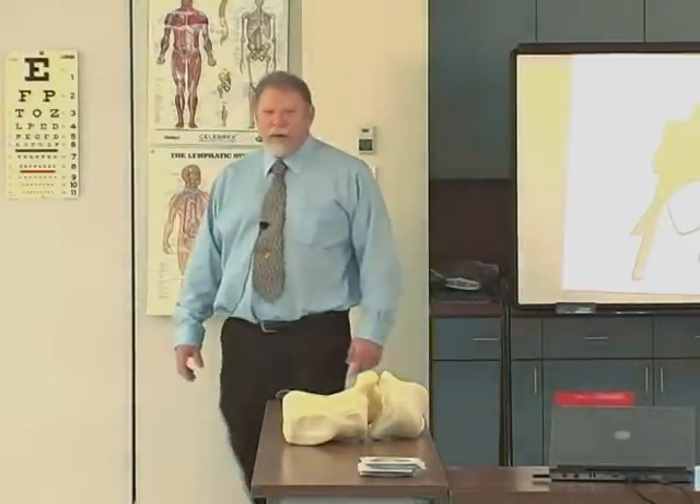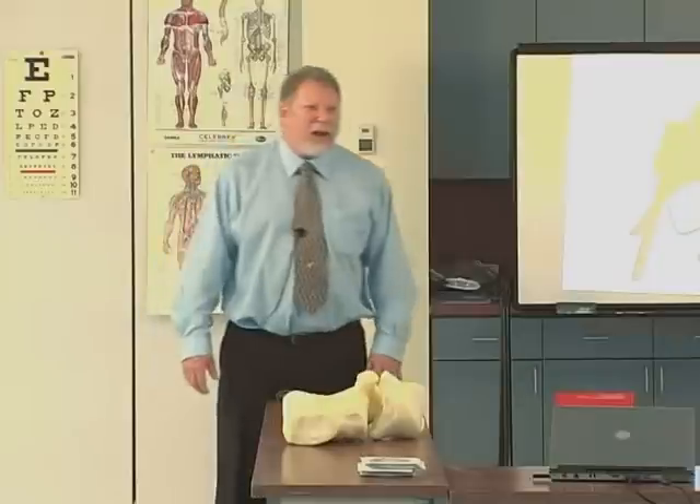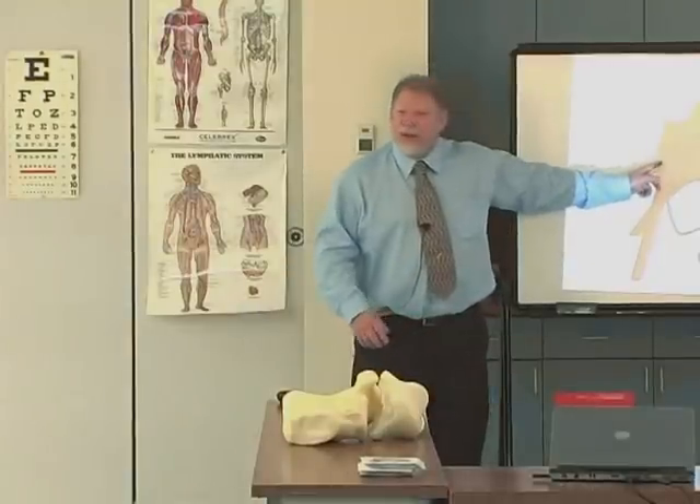We spent nine years in conjunction with the Vanderbilt University Biomedical Engineering Department. We had five interns rotating through, and over a nine-year period we went through numerous permutations. Finally, the answer came to me when I was helping my son with his physics homework. We were studying Pascal's Law: pressure inside an enclosed container is equivalent in all directions. And suddenly a light went off — we have to put it in an enclosed container.